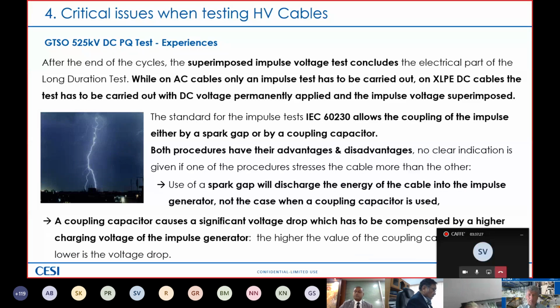Another very important experience that we want to share with you is that after the end of the cycle, as I mentioned, we need to deliver a superimposed impulse voltage test in order to verify the whole cable system. As I said, while an AC cable only has to withstand an impulse test, with an XLPE DC cable the test has to be carried out with the DC voltage permanently applied and switching or lightning impulses superimposed. And according to IEC 60230, there are two possibilities of coupling the impulse, either by a spark gap or by a coupling capacitor.